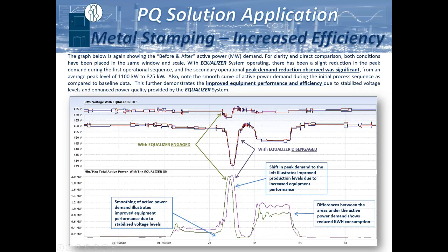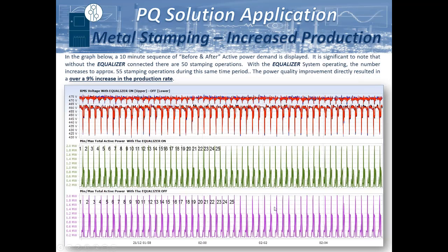So once we're able to raise that voltage level and maintain a very, very tight bandwidth, now all of a sudden you can see in this green line, it's just a smooth transition up. And there's actually a little bit of a leftward shift because the equipment is able to perform in a much better environment and power quality conditions. It's actually enabled it to perform its task in a much more efficient manner. And you can also see the difference in areas between the two lines is actually its kWh savings. So it's quite significant.